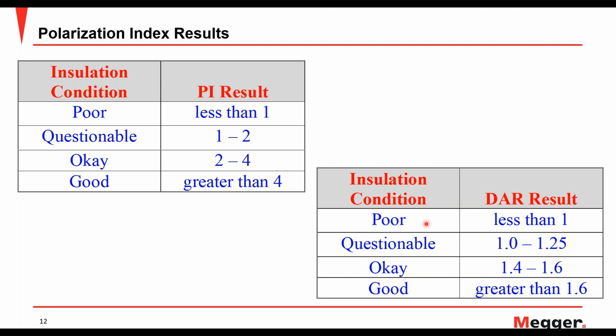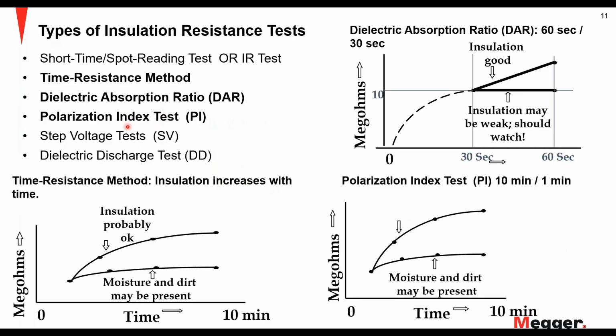The reason being that your 1 minute is at the bottom and 10-minute is at the top. So if your 10-minute reading is lower than your 1-minute reading, obviously your insulation is degrading. Because with time, if you see on the previous screen, the insulation reading should go up as you go up in time. So this is time versus megohm, so it should go up and not down. If it's going down, that means it's a poor insulation.